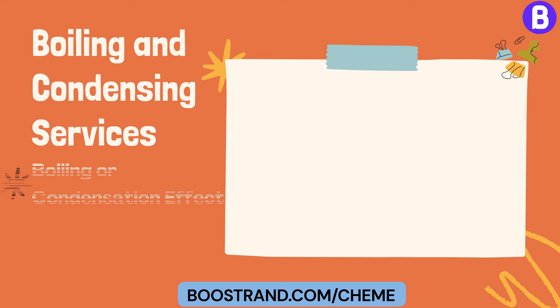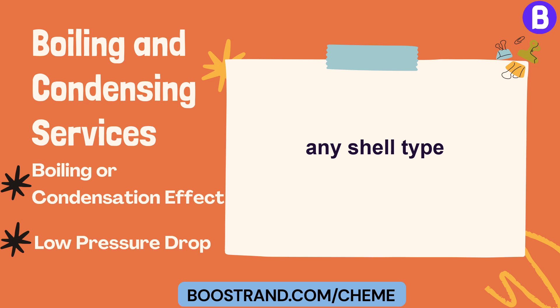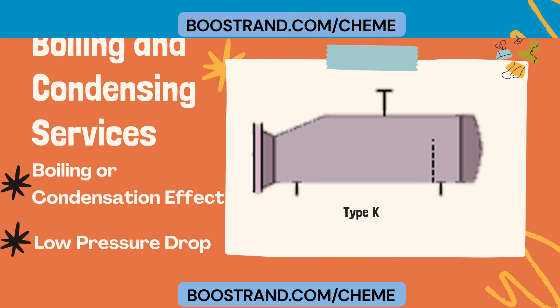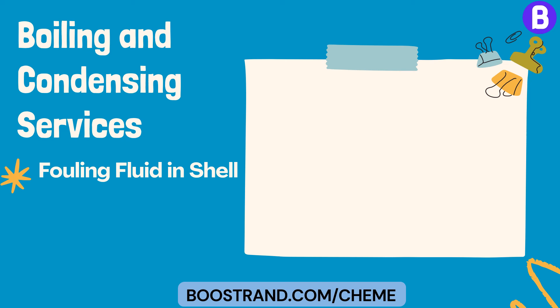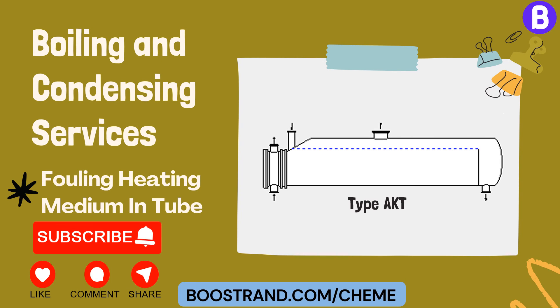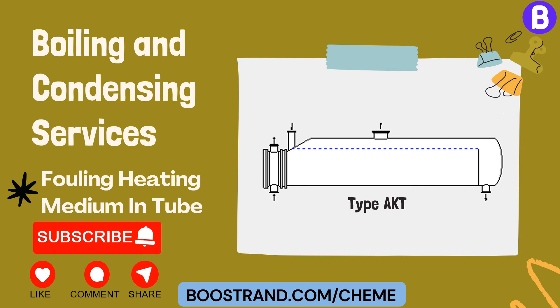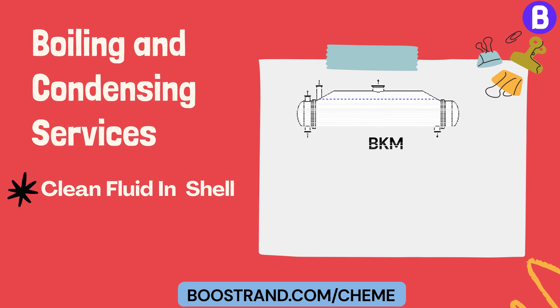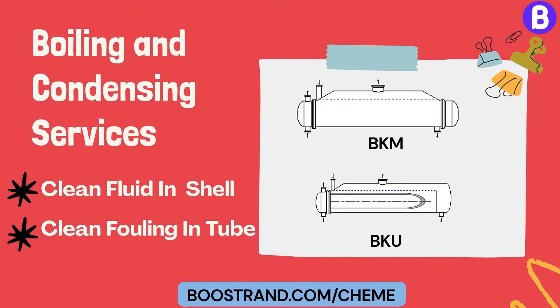For exchangers that exhibit a boiling or condensation effect, we can use any shell type. However, if these exchangers require a very small pressure drop, we can use a kettle type K, such as the case for a kettle reboiler. If we are dealing with a fouling fluid in the shell and a clean fluid in the tube — as is the case for steam reboilers — we can use AKU type. If the heating medium in the tube is fouling, AKT type can be used. If the fluid in the shell is clean, we can use BKM type. If this is accompanied by a clean fluid in the tube, the TEMA type shall be BKU.